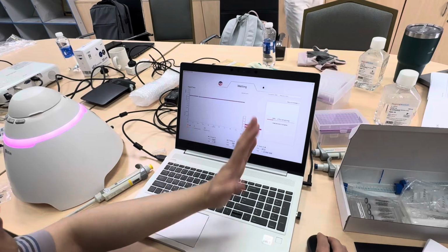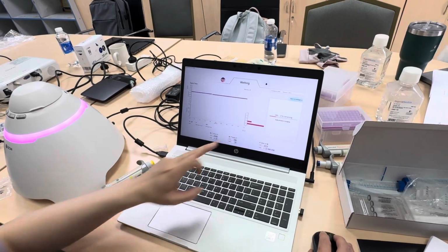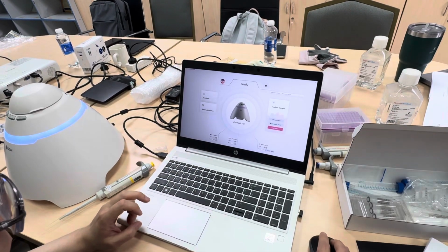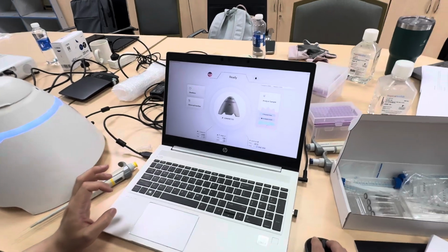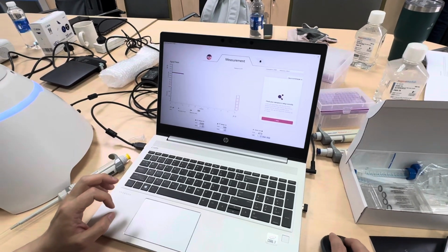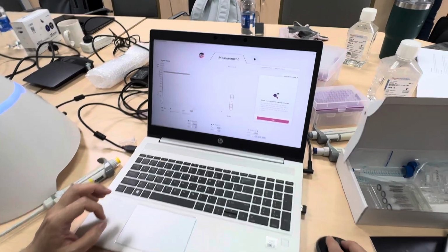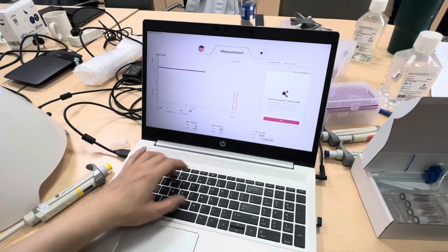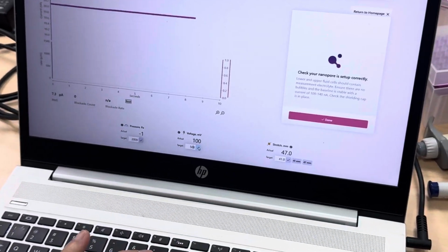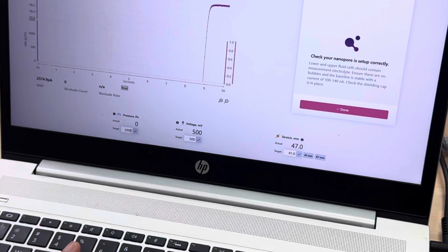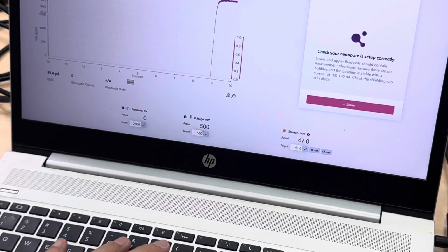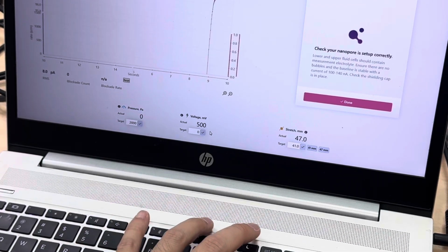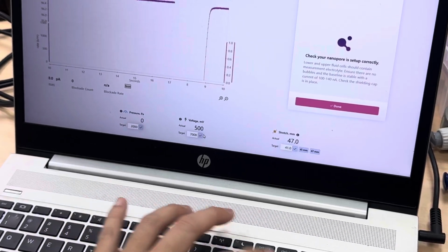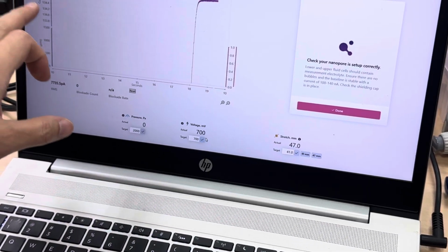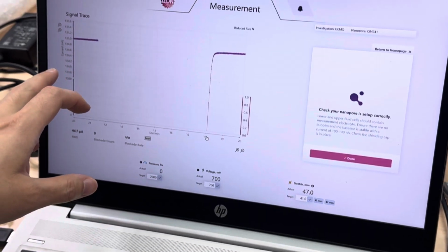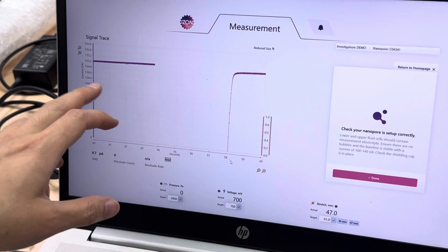Yeah, we just shorten this time. We don't need to wait for this second. We can just start. And once the nanopore is set up, we click Start Analyze. And then increase the voltage to around 500. And then put this to, you need to be 600. Oh, sorry. 700. We need to let the current be above 100, between 100 and 140 nanoamps.